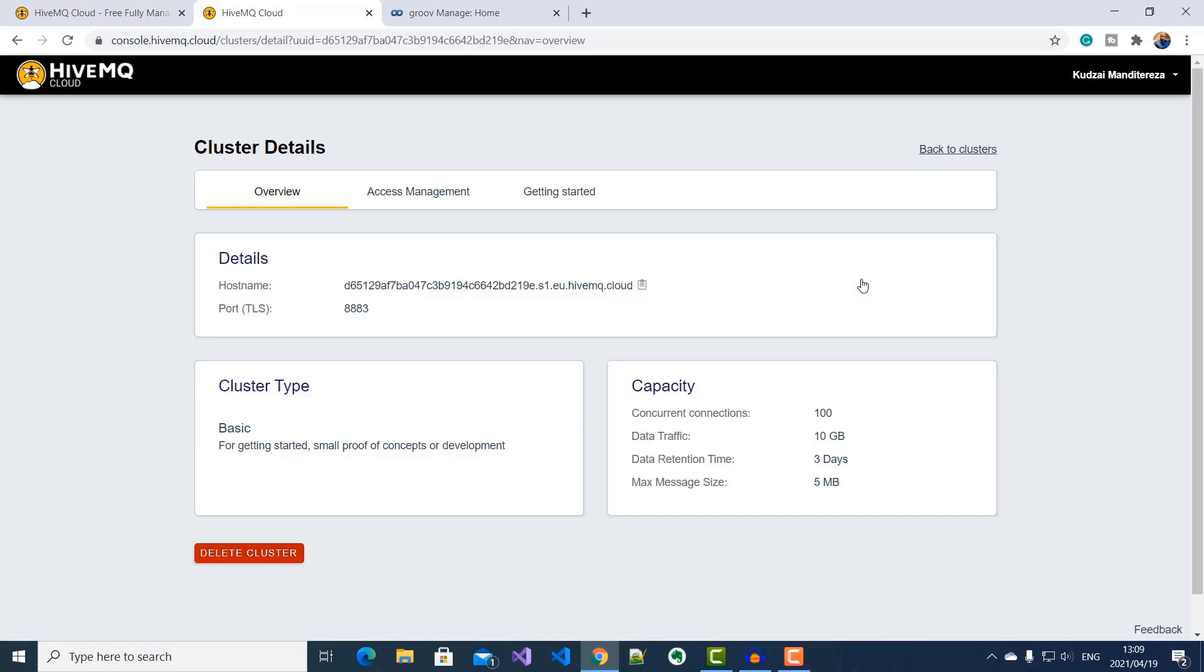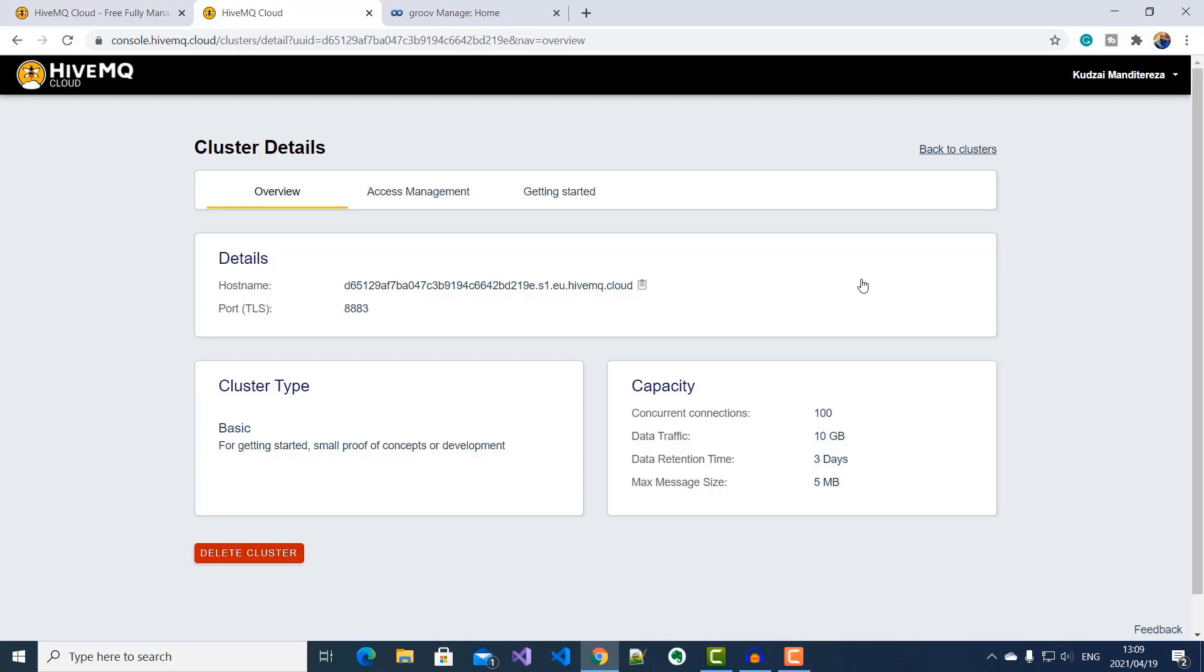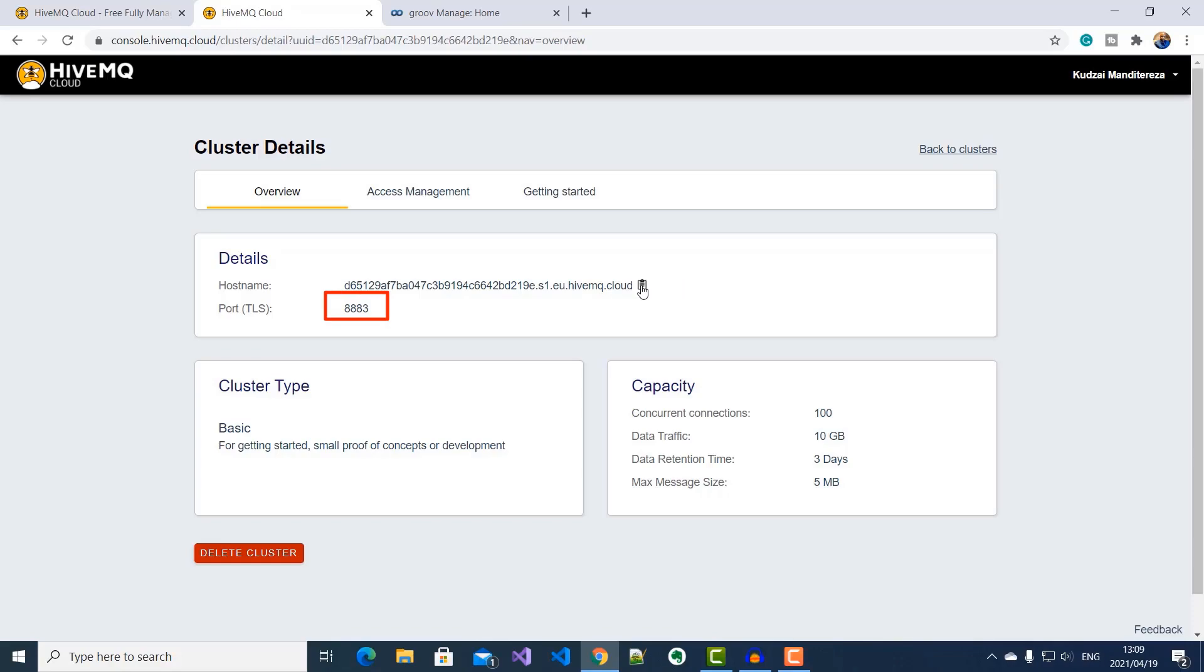Okay, so just by signing up, I had an MQTT broker automatically provisioned for me. Now all I need to do is to copy these details and use them to configure my groov RIO so that I can start publishing the level, temperature and pressure values of our cooling tower as MQTT Sparkplug B messages to this broker. So I'll go ahead and copy the hostname and then I'll note the port number.